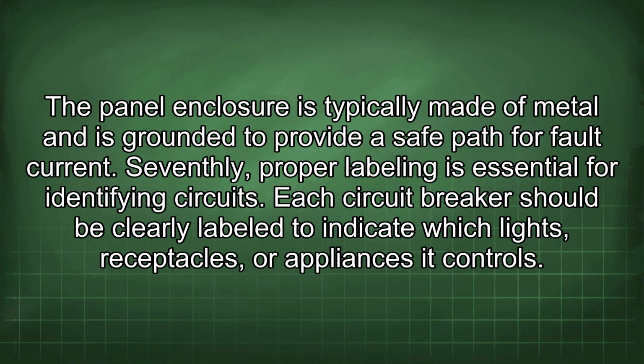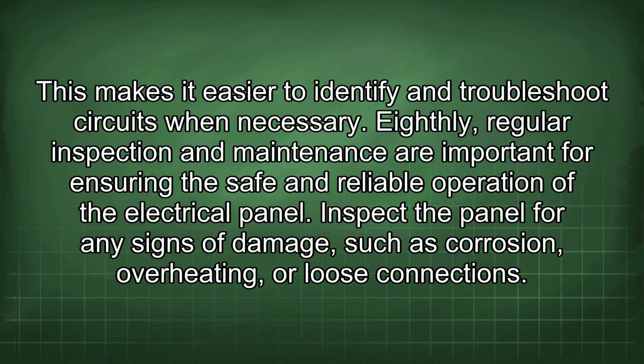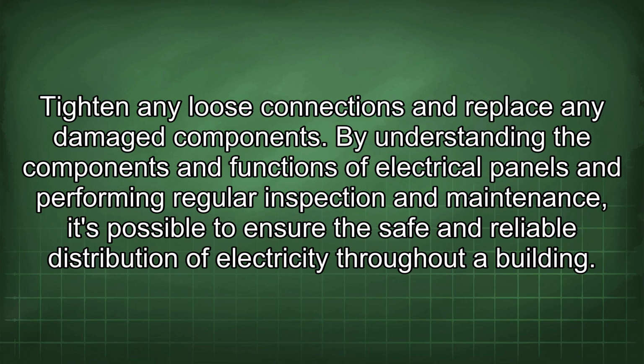Seventhly, proper labeling is essential for identifying circuits. Each circuit breaker should be clearly labeled to indicate which lights, receptacles, or appliances it controls. This makes it easier to identify and troubleshoot circuits when necessary. Eighthly, regular inspection and maintenance are important for ensuring the safe and reliable operation of the electrical panel. Inspect the panel for any signs of damage such as corrosion, overheating, or loose connections. Tighten any loose connections and replace any damaged components.